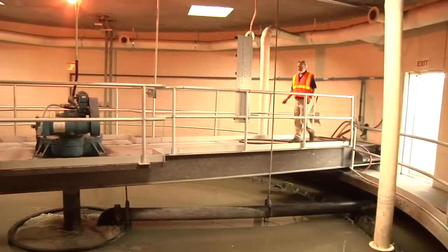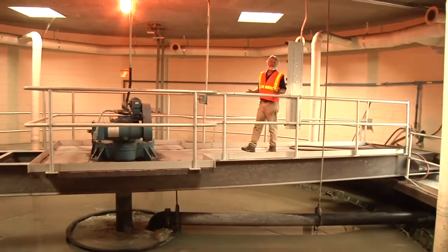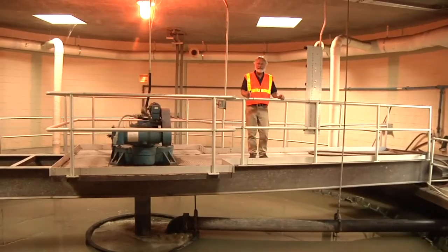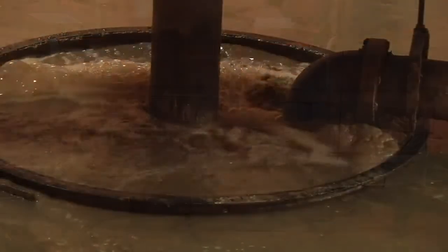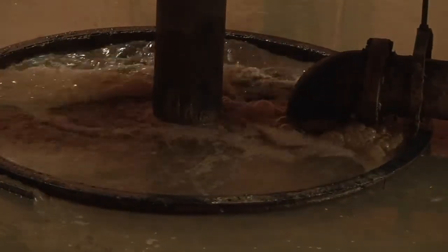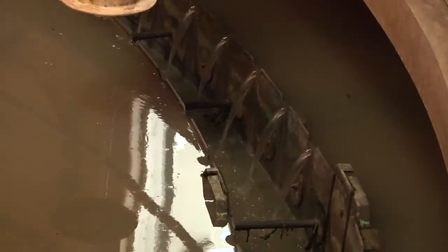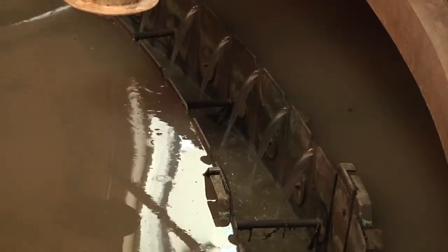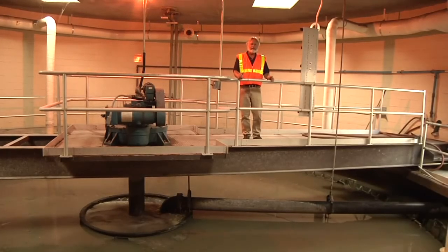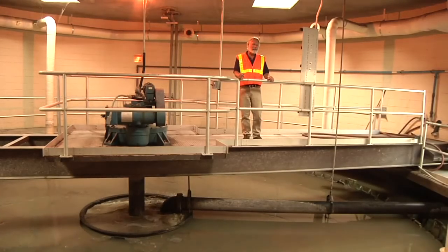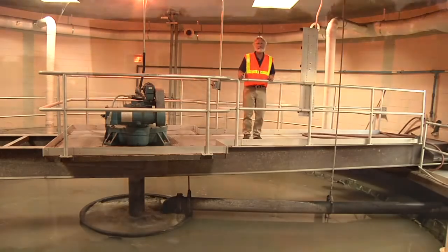This is the sludge thickening process. It's the first step in the solids handling processes, and it's very similar to the clarifiers that we looked at before, where we slow the water down and allow the solids to settle out. But the special feature of thickening is that we're taking our solids concentrations from about 0.5% all the way up to 6% solids. The reason we do that is so that we have less energy to pump the solids and so that we have a better treatment in the remainder of the solids handling processes.